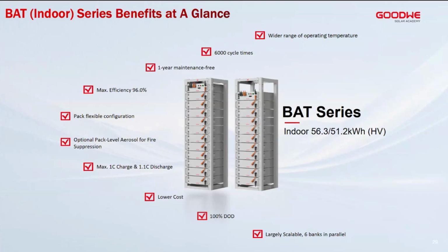It's flexible in terms of configuration, as I mentioned before. You can see the first tower or bank has 11, so the whole rack is full. And the next tower has 10 batteries, so we have an empty slot. So you're flexible in how you can choose and install the sizing of the battery. The battery comes with an optional feature in terms of fire suppression. Every battery module can come with a pack level aerosol for fire suppression. The charge and discharge is 1C for charging, 1.1C for discharge. This ensures that you're able to support your loads at 1C. So if you have an inverter of 50 kilowatt, you only need a full bank, and that is minimum 51.2, and you're able to support a load of up to 50 kilowatt discharge.